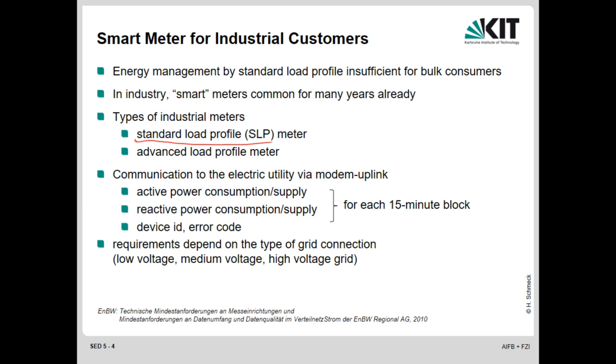And what they do there is, in 15-minute blocks, they send the active power consumption, the reactive power consumption, Blindleistung, and also the device that is measured, and some error code, if the measurement is erroneous or something like that, it's indicated.